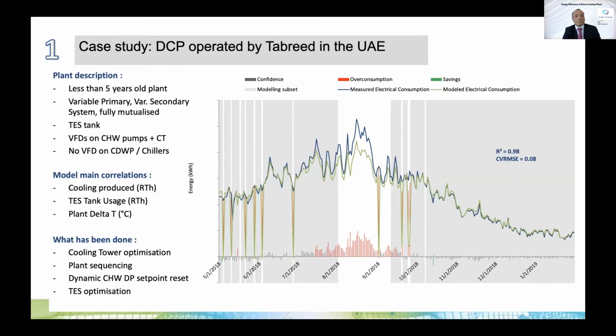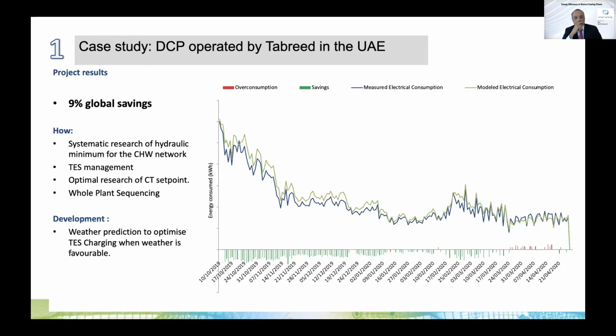We've taken the same approach, deploying an IPMVP method, and we've gone a little bit further than on the Veolia plant since we've deployed the cooling tower optimization, the dynamic chilled water DP set point reset, and in this case, the whole plant sequencing. The results are very satisfying as well. We've achieved 9% global savings on the consumption of the plant, similarly, by doing a systematic research of the hydraulic minimum.